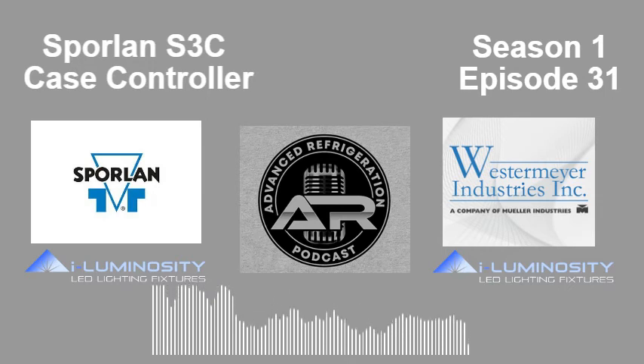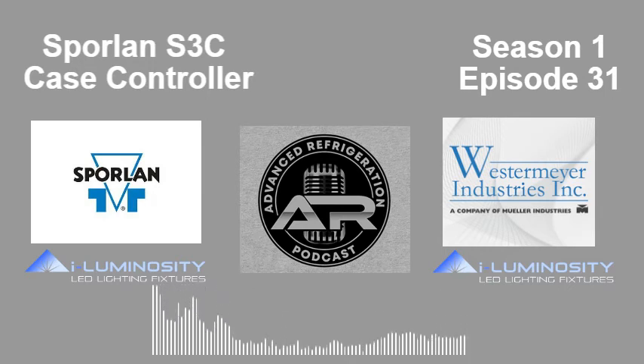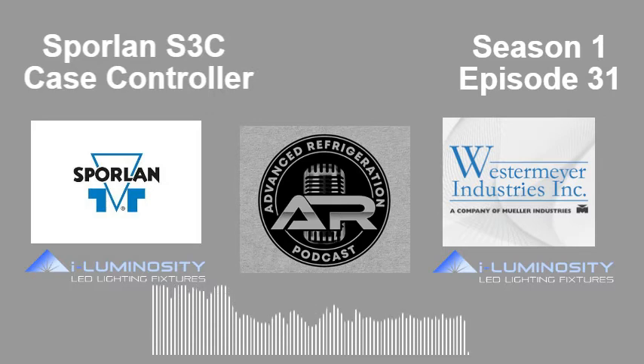There's so much variability in this, and it's tough to have everything managed correctly and input correctly by the OEM. You could argue this list of performance tests that we've got in place would be a really good thing for an installing contractor, if they had the time to go through it. It would be nice to have integrators out at the job site when they're starting up a store. But that's tough, because how many store startups are going on at the same time? Even if you had somebody dedicated to that function from our organization, to go through all these steps at every startup would be really tough to pull off. But we could argue that might be where we need to go.